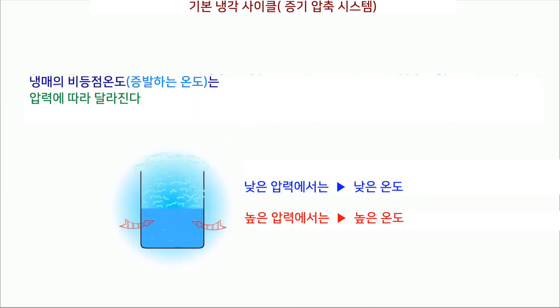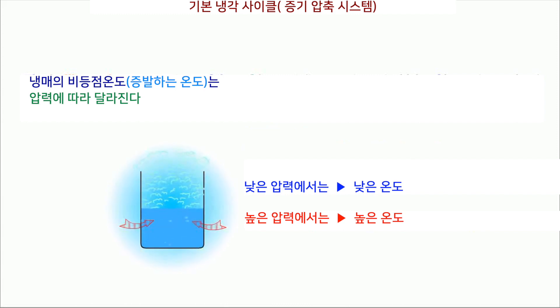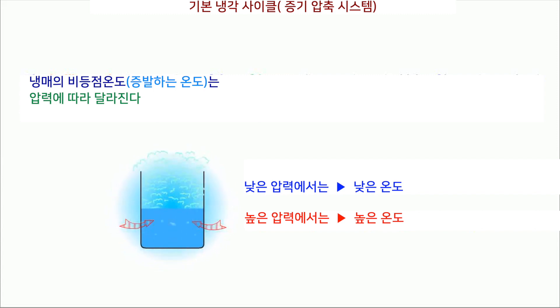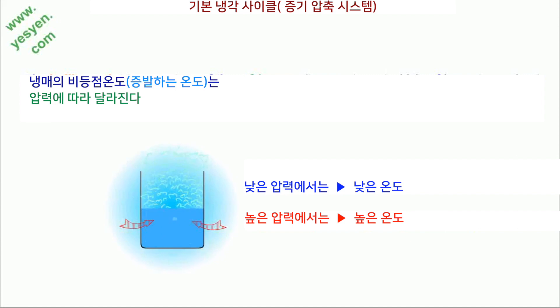The boiling point temperature of the refrigerant — that is, the temperature at which the refrigerant vaporizes — depends on the pressure. Lower the pressure, lower the temperature. Higher the pressure, higher the temperature.